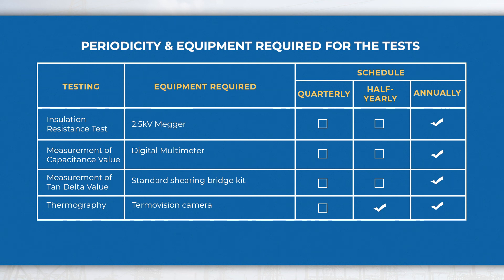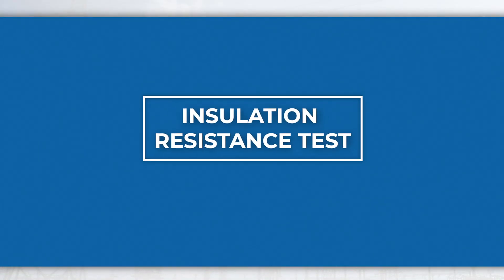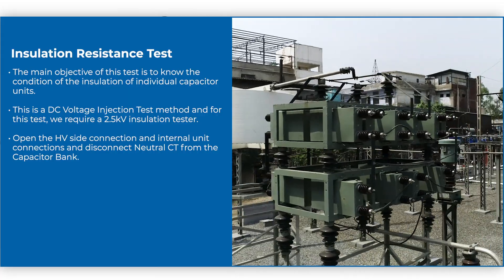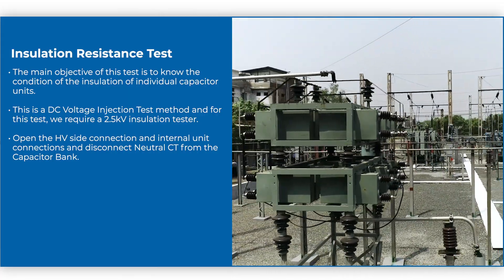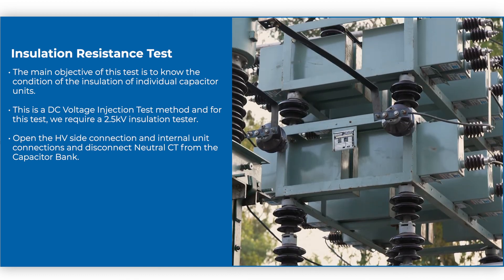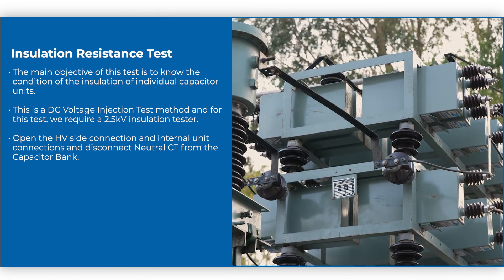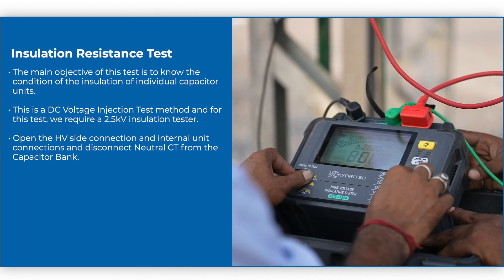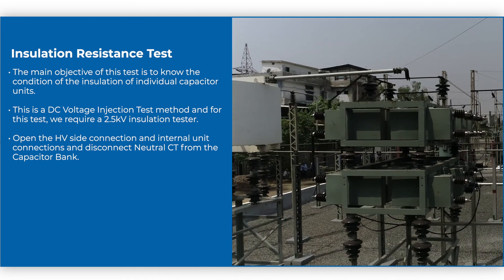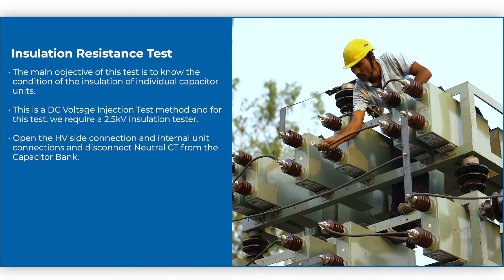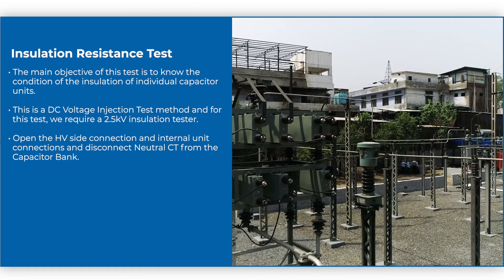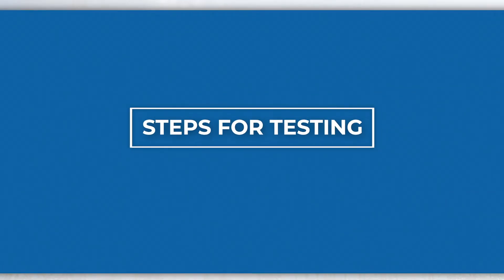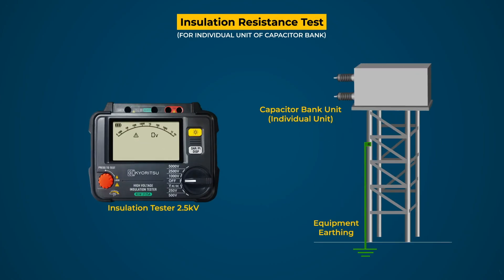Testing of capacitor bank: as per the maintenance schedule, these tests shall be carried out at regular intervals as mentioned in the table. Insulation resistance test: the main objective of this test is to know the condition of the insulation of individual capacitor units. This is a DC voltage injection test method and requires a 2.5 kV insulation tester. Open the HV side connections, internal unit connections, and disconnect the neutral CT from the capacitor bank.